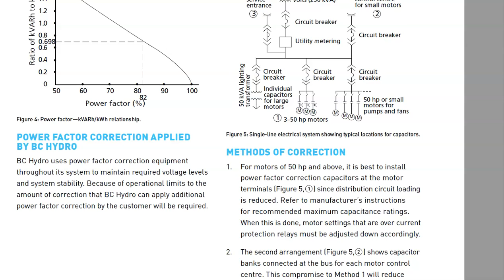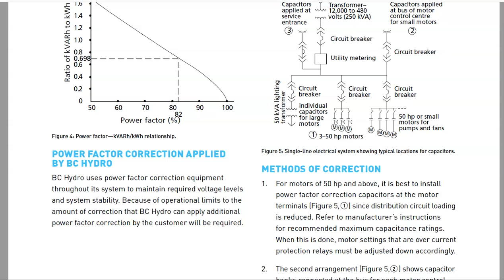Okay, so for motors of 50 horse and above, we want to directly put them at the motor because it's going to drop the line current all the way to the motor. That means that the voltage drop to the motor, the VA of the motor, all of that stuff is going to be dropped. Now, we can place it downstream of the contactor. If we do place it downstream of the contactor, between the contactor and the motor itself, we are going to have to adjust our overloads for that. They talk about that inside of here. They talk about that inside of your module as well.